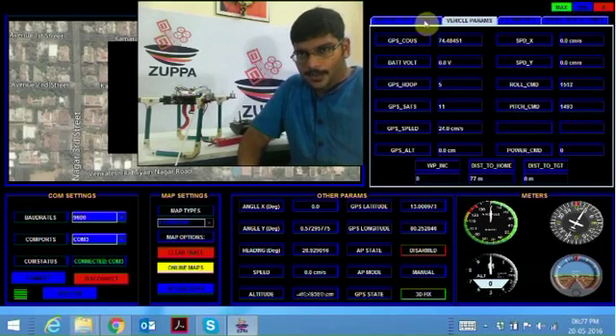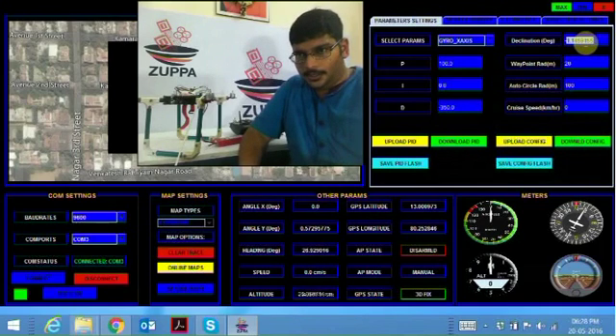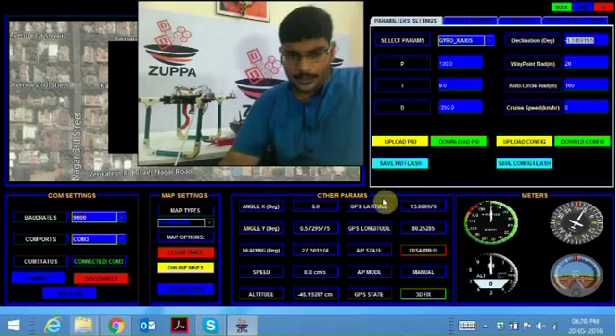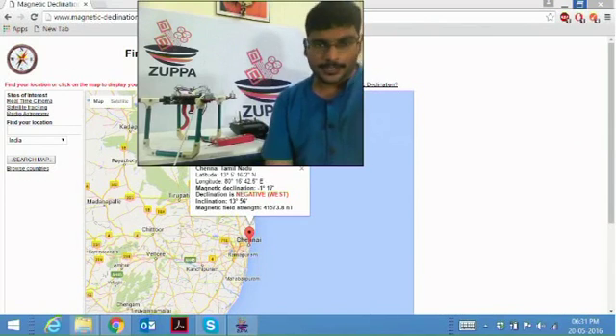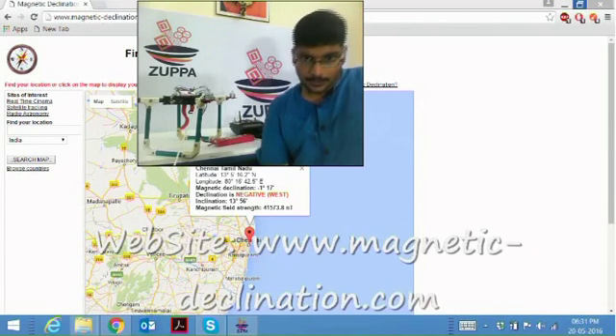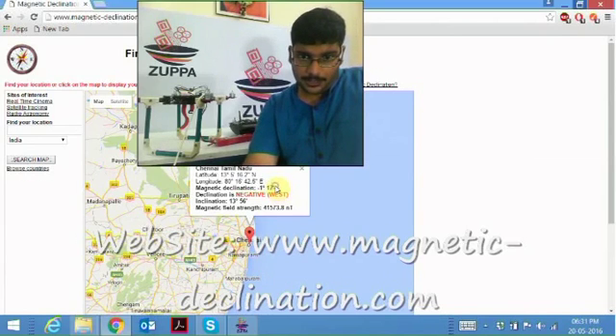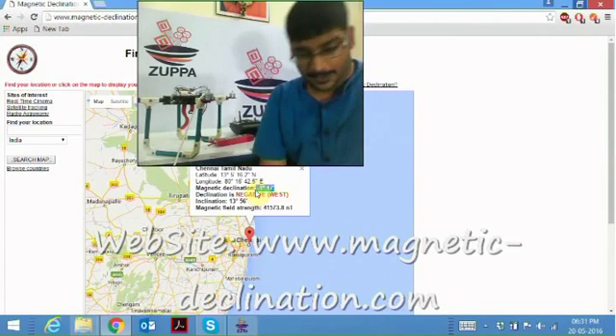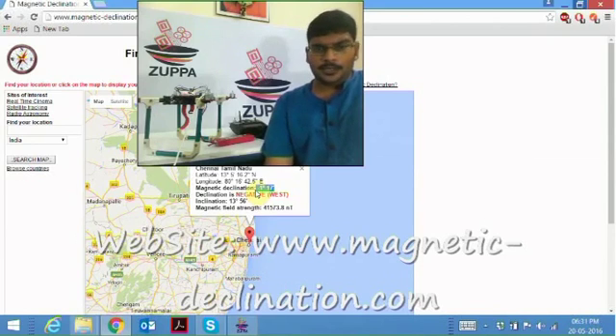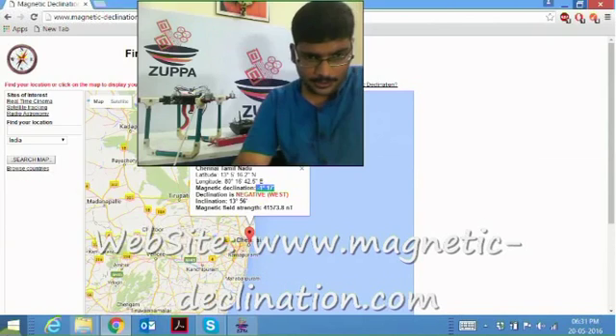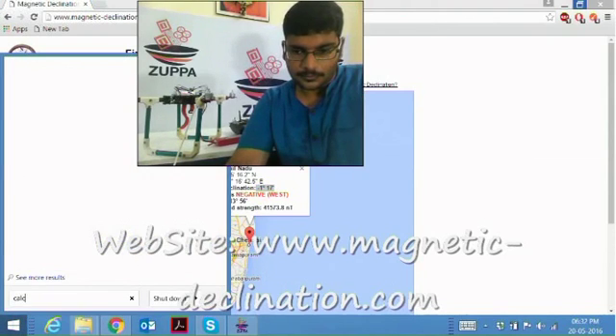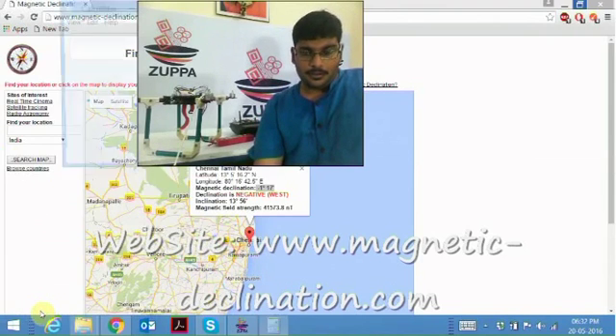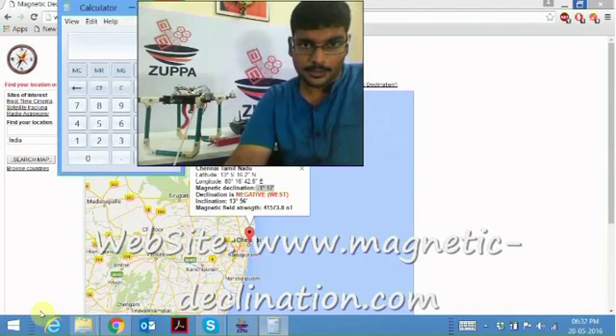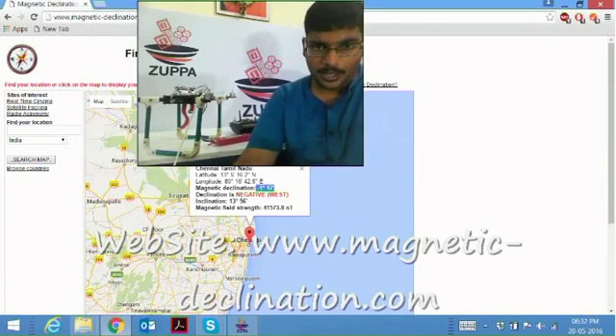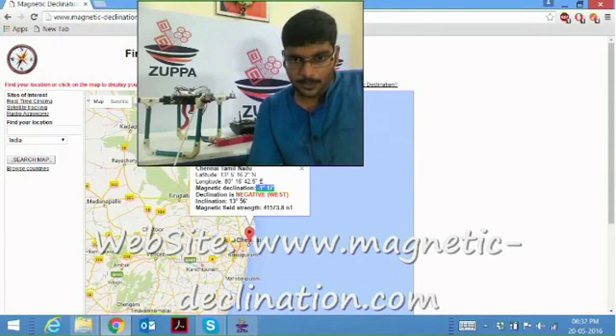Now on the last part of calibration, we need to first set the declination in terms of degrees. So you click on this, and as you can see, the website www.magnetic-declination.com has opened, and based on your internet connection it gives you the magnetic declination. The declination given here is minus 1 degree 17 minutes. 17 minutes in terms of degrees is 17 by 60, so you just do some fast math. 17 divided by 60 is 0.28, so my magnetic declination offset is minus 1.28 degrees.